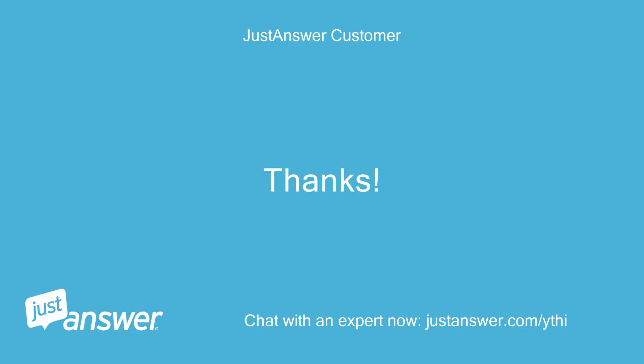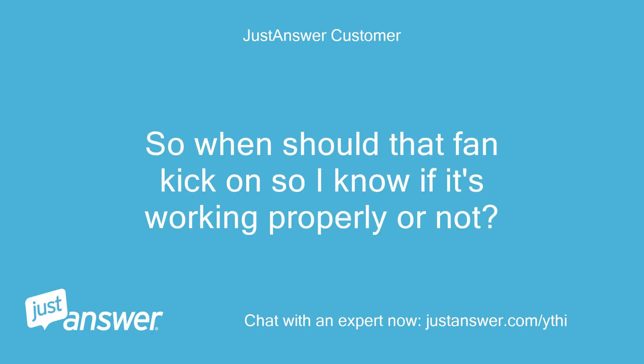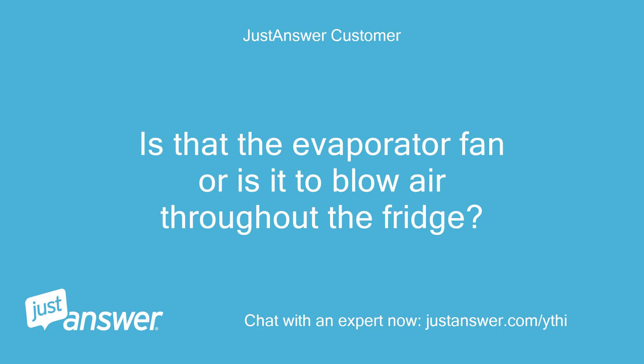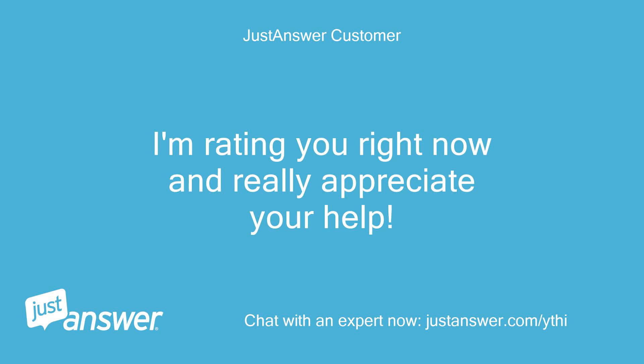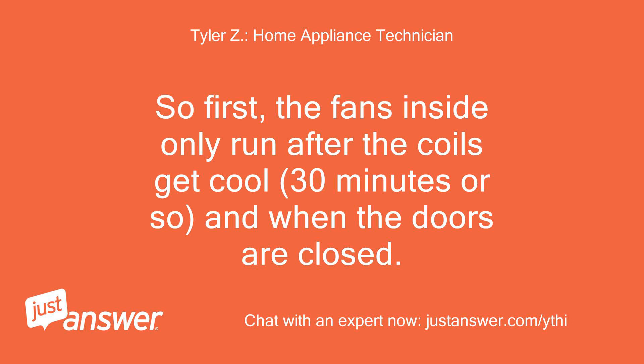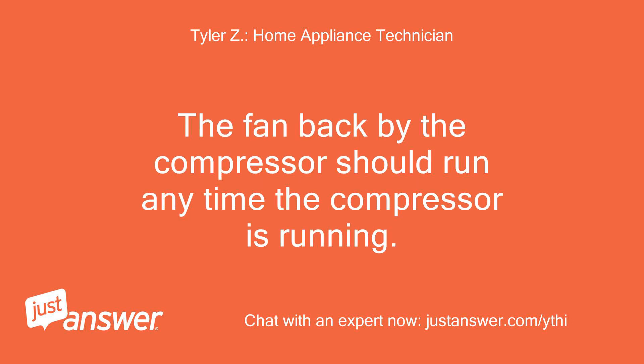So when should that fan kick on so I know if it's working properly or not? Is that the evaporator fan or is it to blow air throughout the fridge? I'll order one anyway just to be safe. Tyler responds: The fans inside only run after the coils get cool — about 30 minutes or so — and when the doors are closed. The fan back by the compressor should run any time the compressor is running.